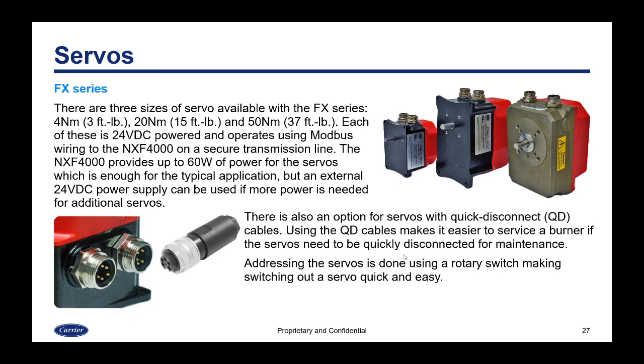There's also an option for the servos to be provided with quick disconnect cables. Using the quick disconnect cables makes it easier to service a burner if you need to remove the servos quickly. Addressing the servos is done using a rotary switch, making switching out a servo very quick and easy.